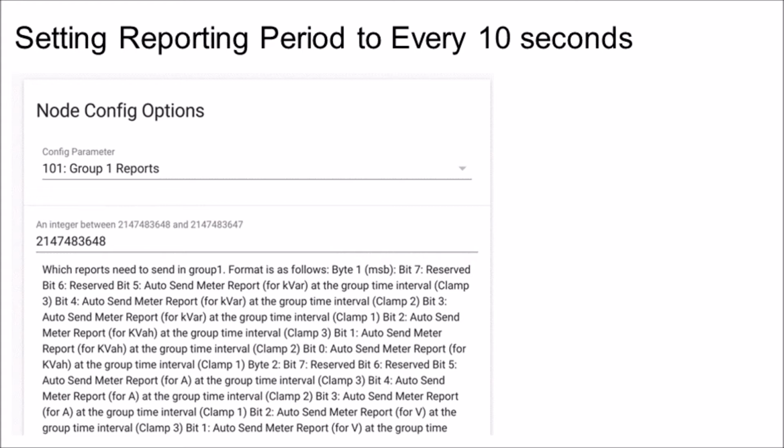And the solution turned out to basically find the reporting settings within the device configurations and set them to a 5 or 10 second reporting period. Some of these devices were reporting every 2 minutes instead of every 5 to 10 seconds, and that was causing our graph to look weird. So I then set the settings to 5 seconds, and then on Grafana, I graph to a 10-second interval, and all of a sudden the graph shows a much higher degree of resolution.